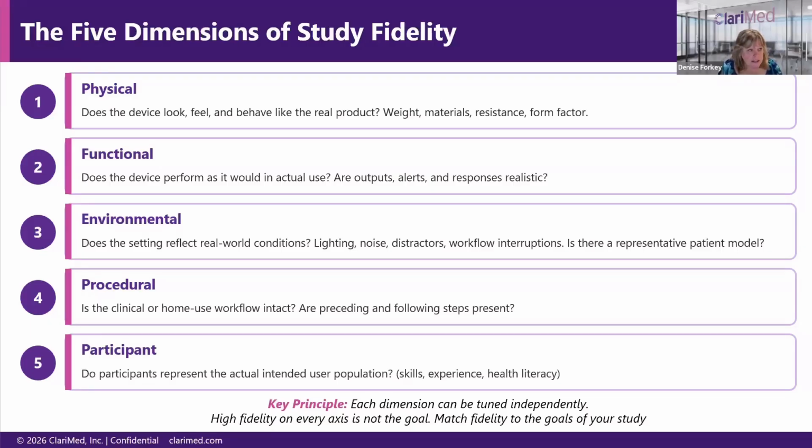And for formatives, one of the things that comes up is that the FDA says, yeah, it's okay for you to use employees at a manufacturer. Well, I think we need to really think about that carefully. If you're having engineers use a product that's going to be used by the general population, then is that really representative of an actual user's experience with the product? Probably only a very, very, very small percentage of the population have that level of education. So make sure you're smart about it.